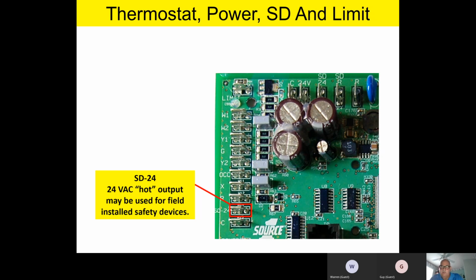Instead, go up to the top part of the board where we've been discussing the SD24 and the SDR. Remove that jumper at the top of the board, and then put your safety circuits, your aftermarket or field installed safety circuits, up there. Don't mess around with it down by the thermostat terminals. A more reliable place is the SD24 and SDR jumper that we've talked about, if you want to put field installed dry relay contact switches in there for safety circuits. Any questions or comments on that?